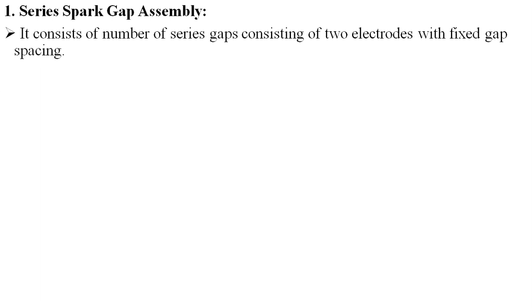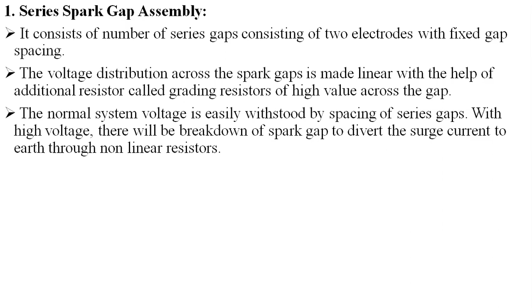Series spark gap assembly: it consists of a number of series gaps, each consisting of 2 electrodes with fixed gap spacing, and the voltage distribution across the spark gaps is made linear with the help of additional resistors called grading resistors of high value across the gap. The normal system voltage is easily withstood by the spacing of series gaps. With a high voltage, there will be breakdown of the spark gap to divert the surge current to earth through non-linear resistors. If the voltage variations are comparatively slow, then the influence of grading resistors over that of spark gaps prevents the sparkovers that may be caused by slow changes in voltage, maybe because of internal over voltages during the switching operations, which may not be hazardous to the system.